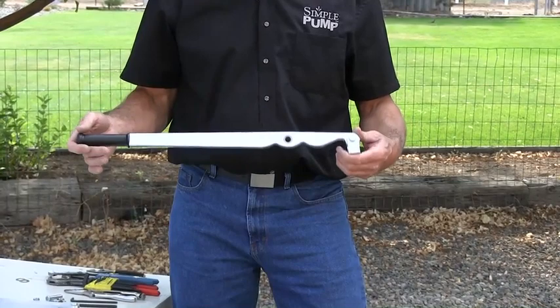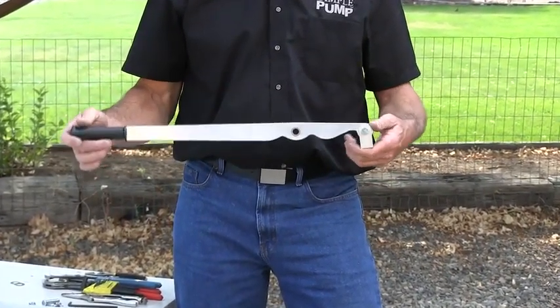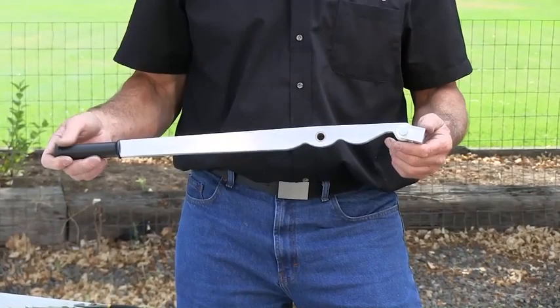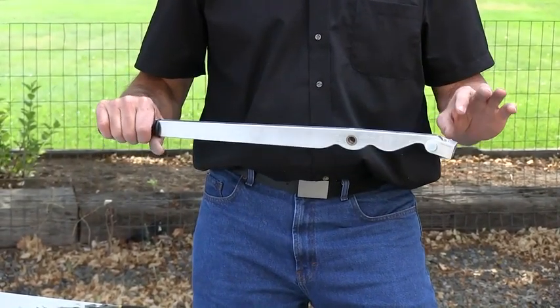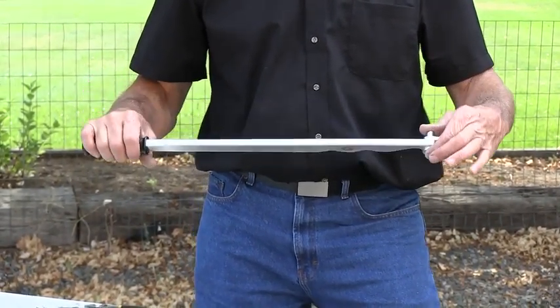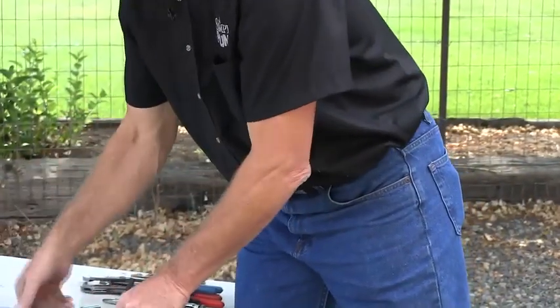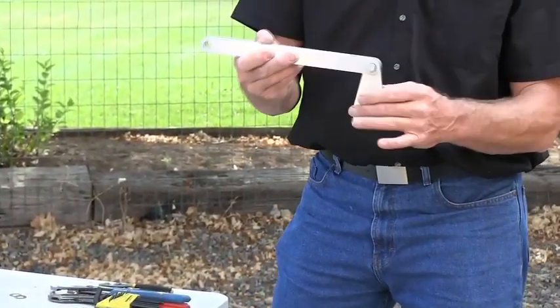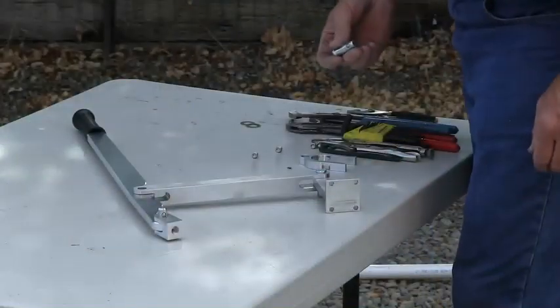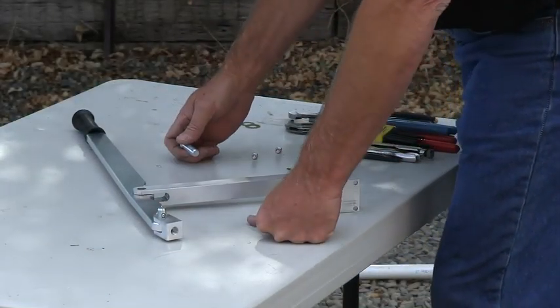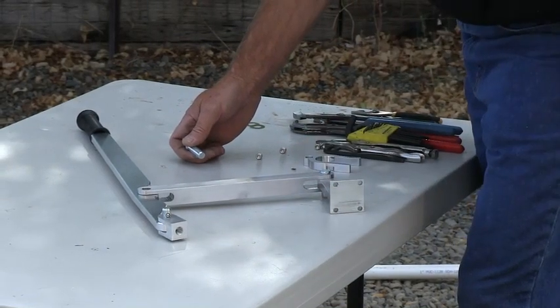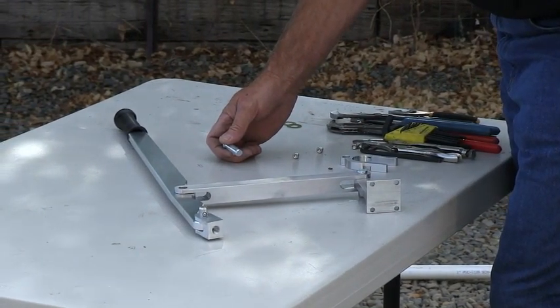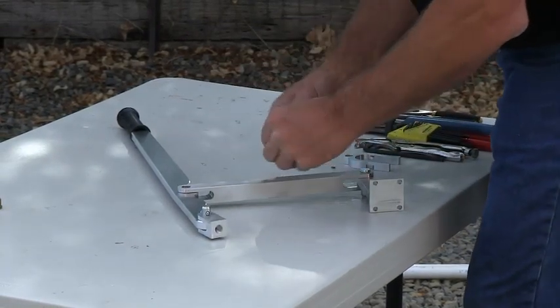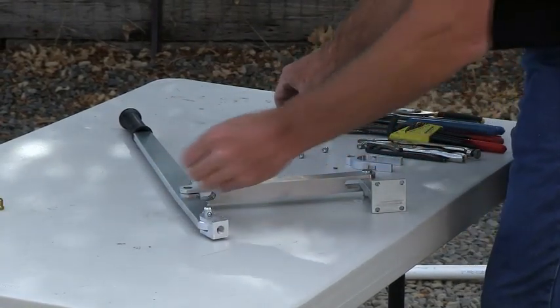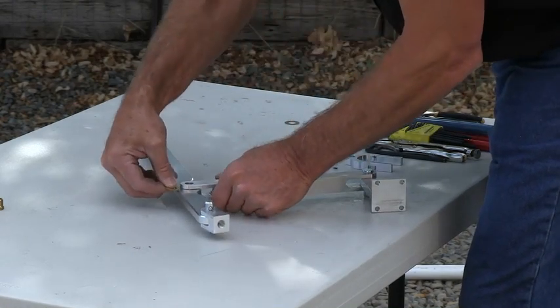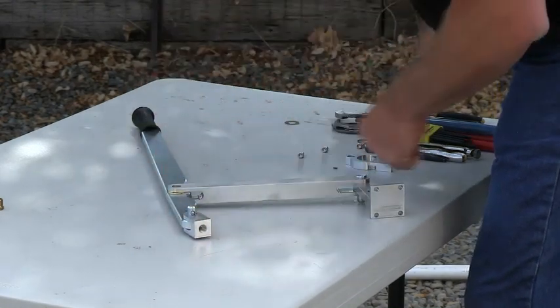The 24-inch or 36-inch lever arms are supplied pre-assembled to the extent that we can. We assemble the clevis, the 2 brass shims, and the clevis pin, and then the mating mechanism, the lever bracket, the lever link arm, and the clevis pin in the shims. The easiest way to put these 2 pieces together, and actually suggests that you do it before trying to attempt to assemble them to the pump head, is to put them on a flat surface and introduce the first shim between the 2 mating parts.